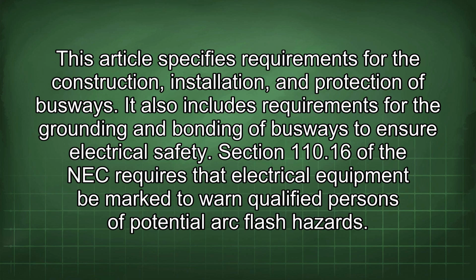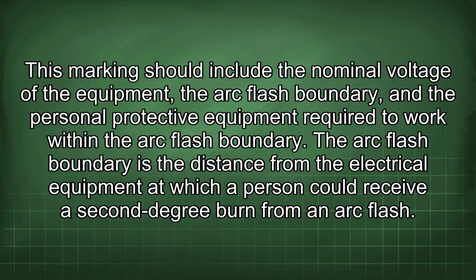Section 110.16 of the NEC requires that electrical equipment be marked to warn qualified persons of potential arc flash hazards. This marking should include the nominal voltage of the equipment, the arc flash boundary, and the personal protective equipment required to work within the arc flash boundary.